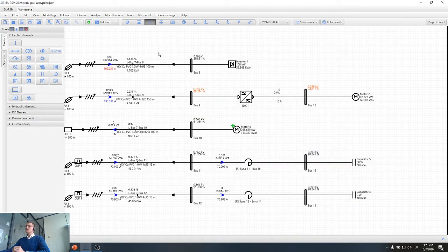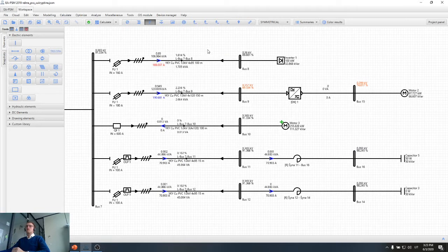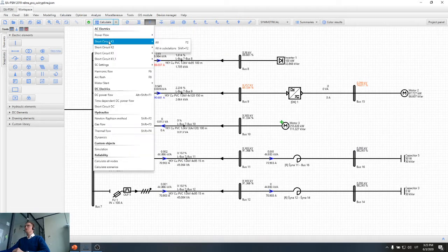So these calculations are very important for protection coordinations, and I would say that these are classical calculations. However, nowadays we can also use arc flash protection calculation. While we have software, it is easy to calculate short circuits, and also easy to estimate protection operation times. So in our software, users can automatically find the short circuit current and the operation time of the protection devices, and this allows us to calculate arc flash.